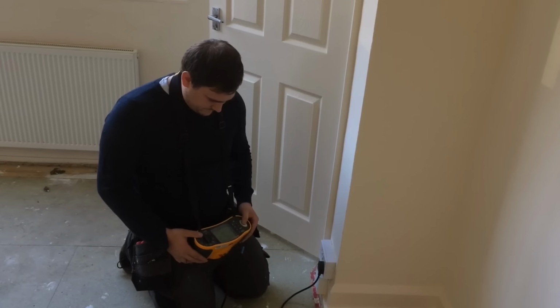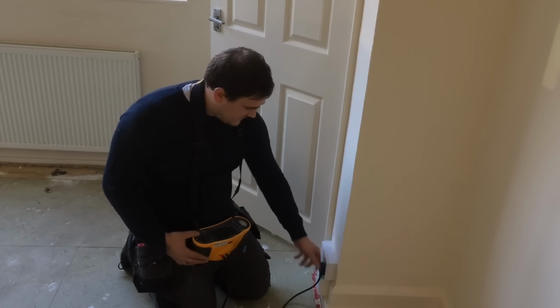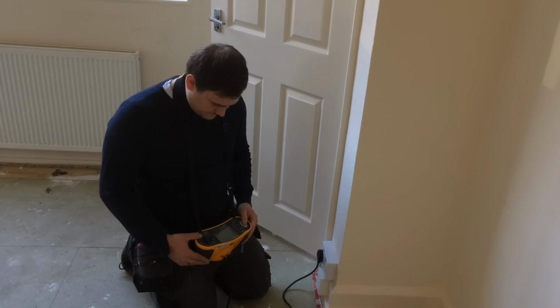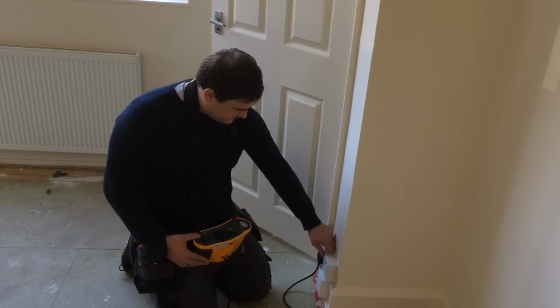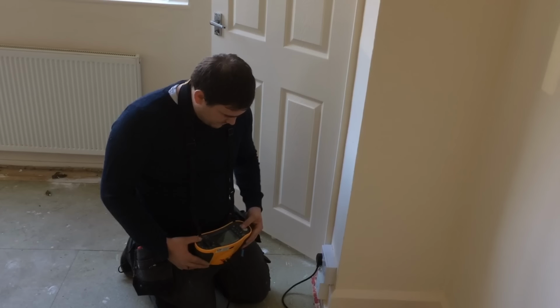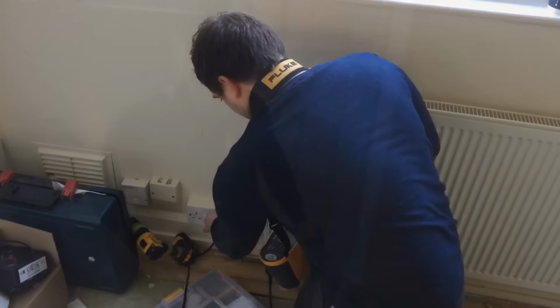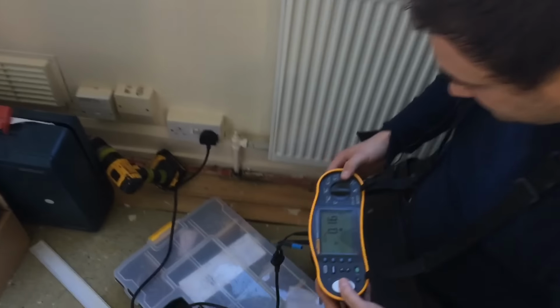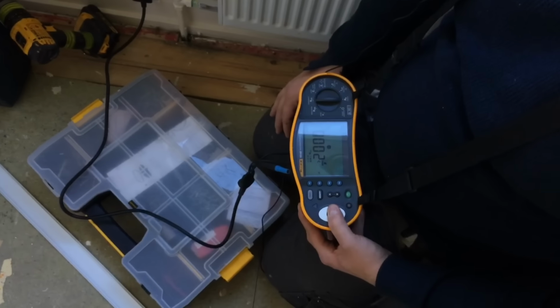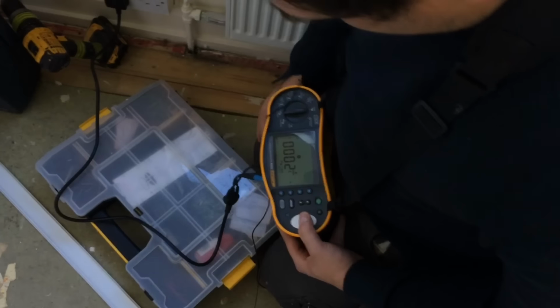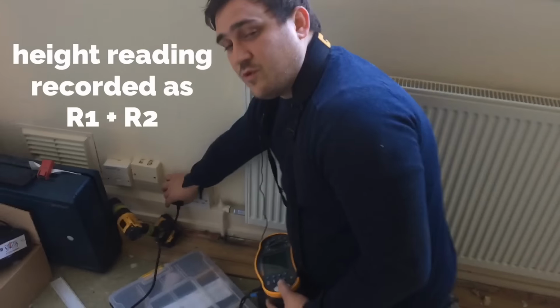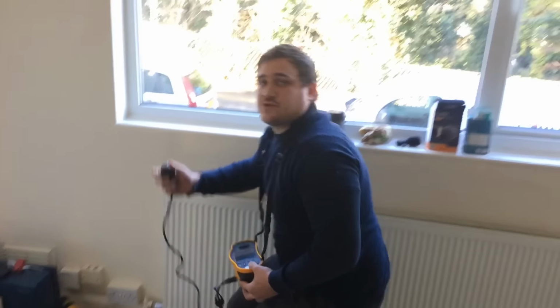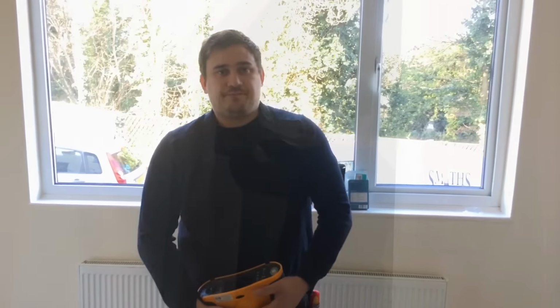0.12, polarity confirmed. 0.14, polarity confirmed. 0.16, again polarity. 0.18. All were within our 0.05 fluctuation of our calculated reading.